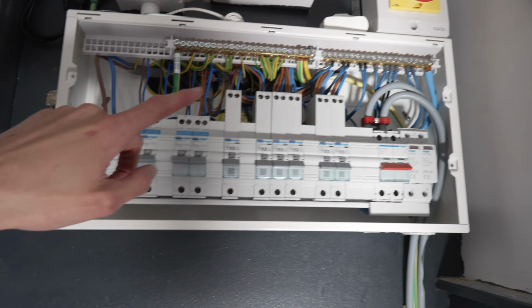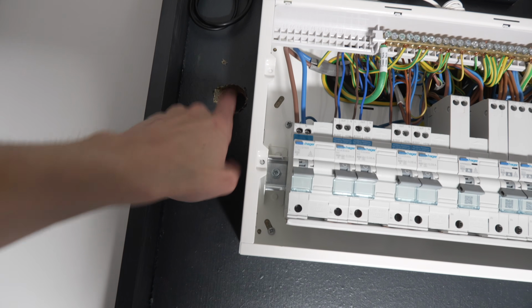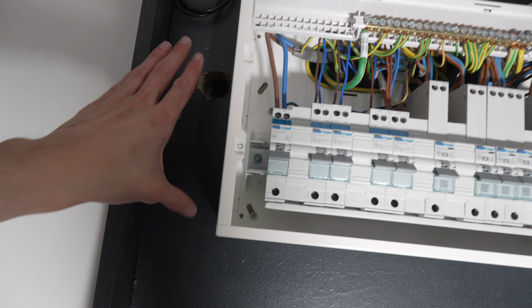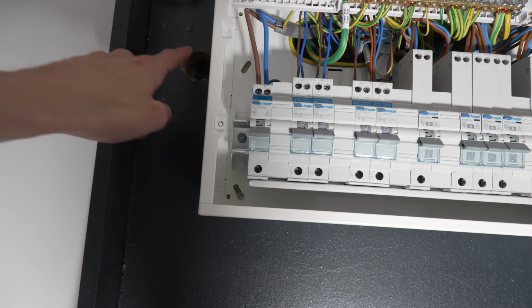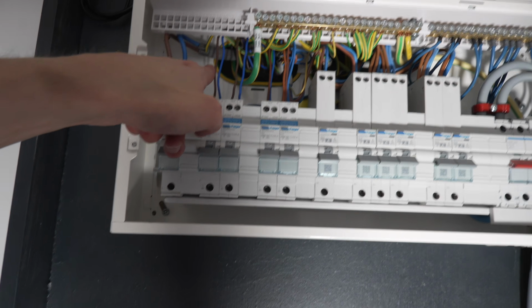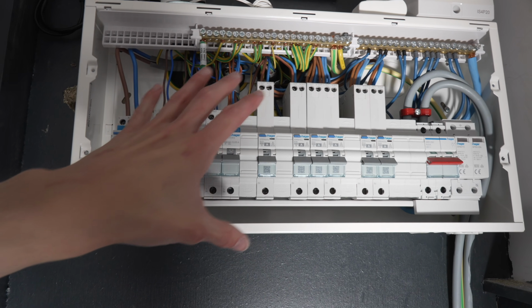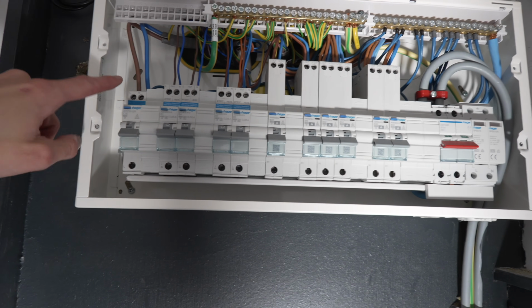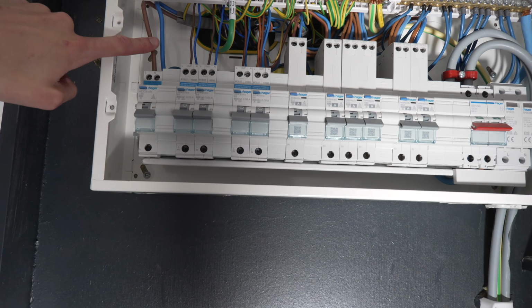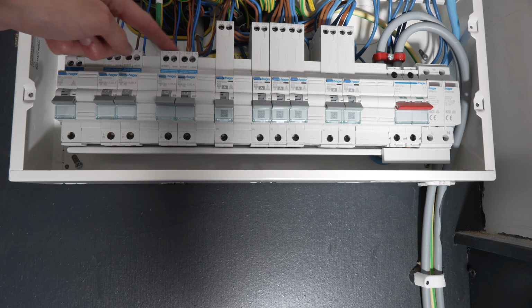So what I've done here to install the CTs is I've drilled a little hole here for the CT cables to go through. This is where I'm mounting the monitoring board, and there's a complete empty void here so I can get the cables through here and into the back of the board. In terms of circuits, as we saw before, we've got the solar circuit, that's going to be easy to install. The lighting circuits, we can again pull those two lines forward and put those through one CT.